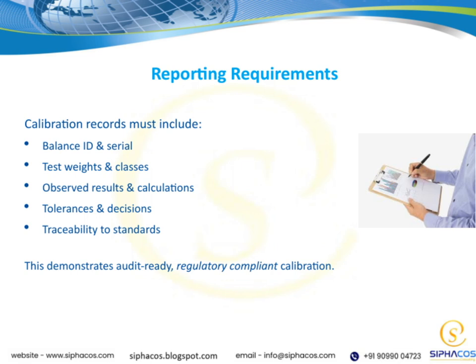Additionally, recording the tolerances and the decisions made based on those tolerances is crucial for compliance and quality assurance. And of course, traceability to standards must be documented. This traceability is what demonstrates that our calibration is audit-ready and meets regulatory requirements. Overall, these detailed records not only support compliance, but also reinforce our commitment to maintaining high calibration standards across all our equipment.